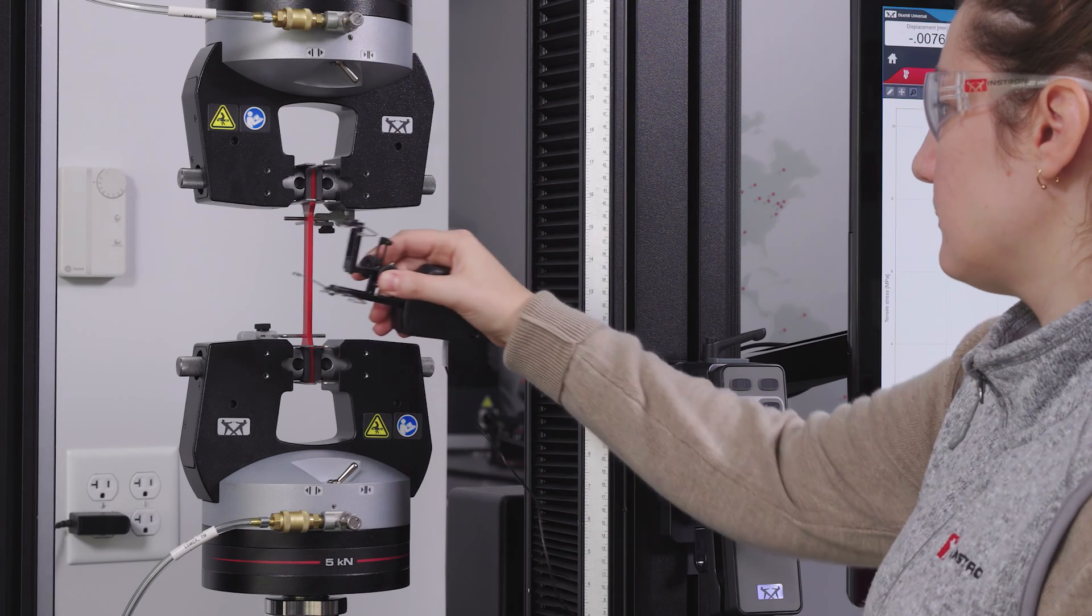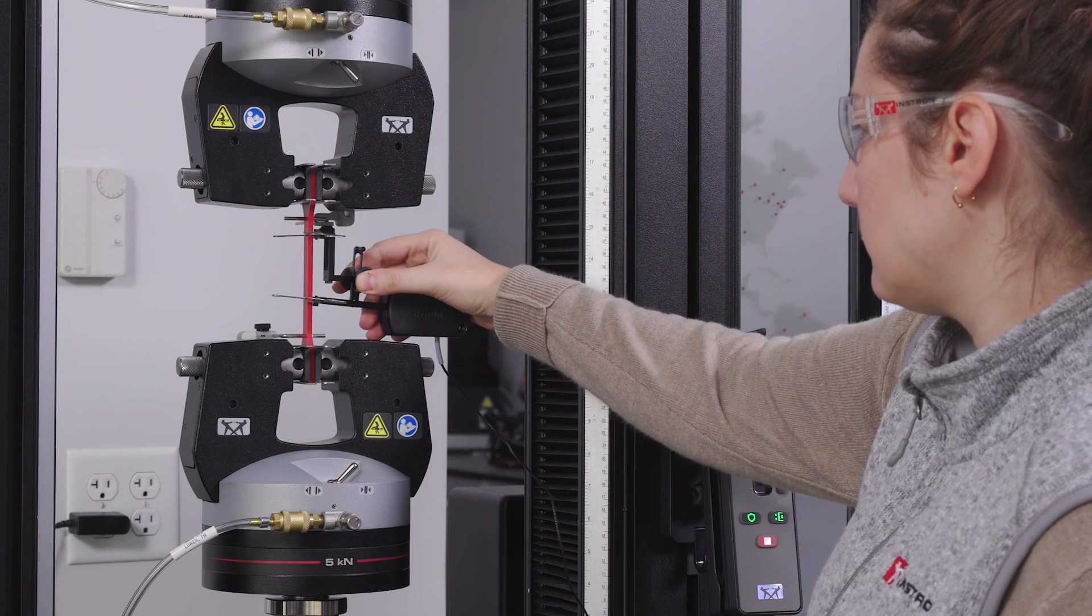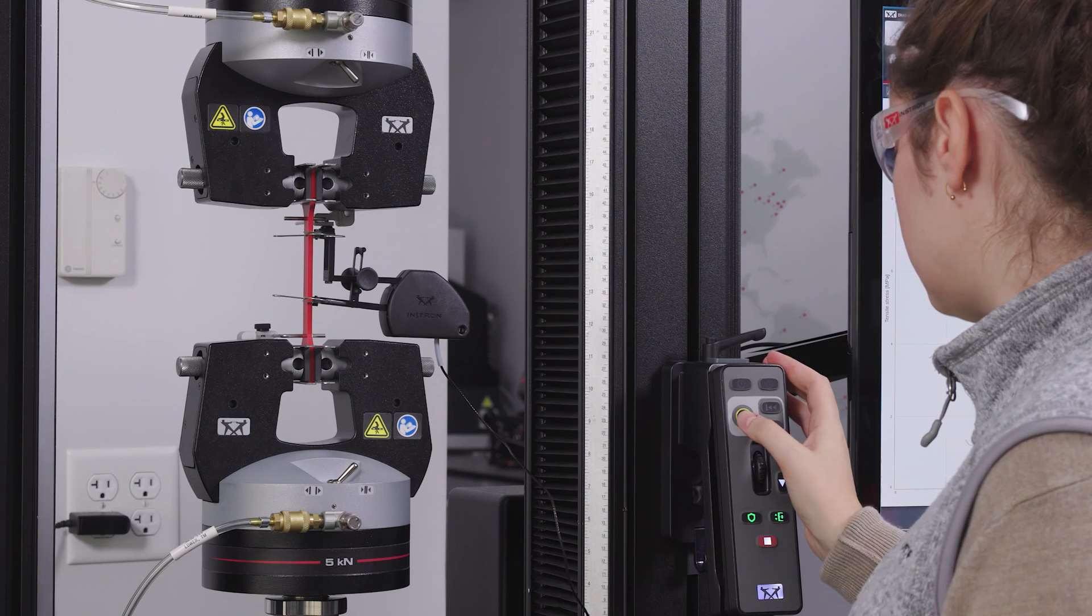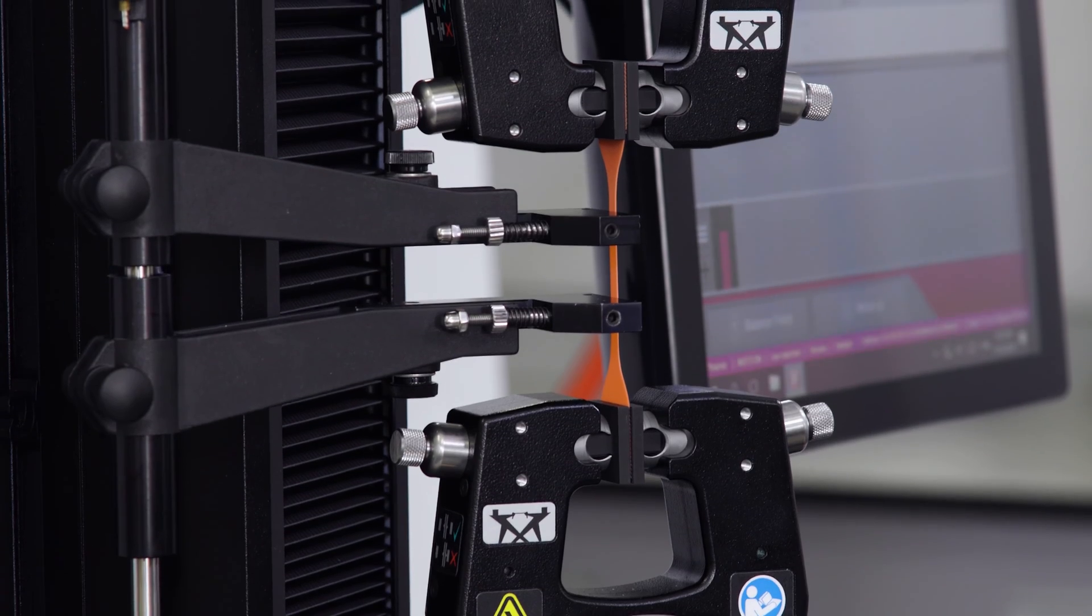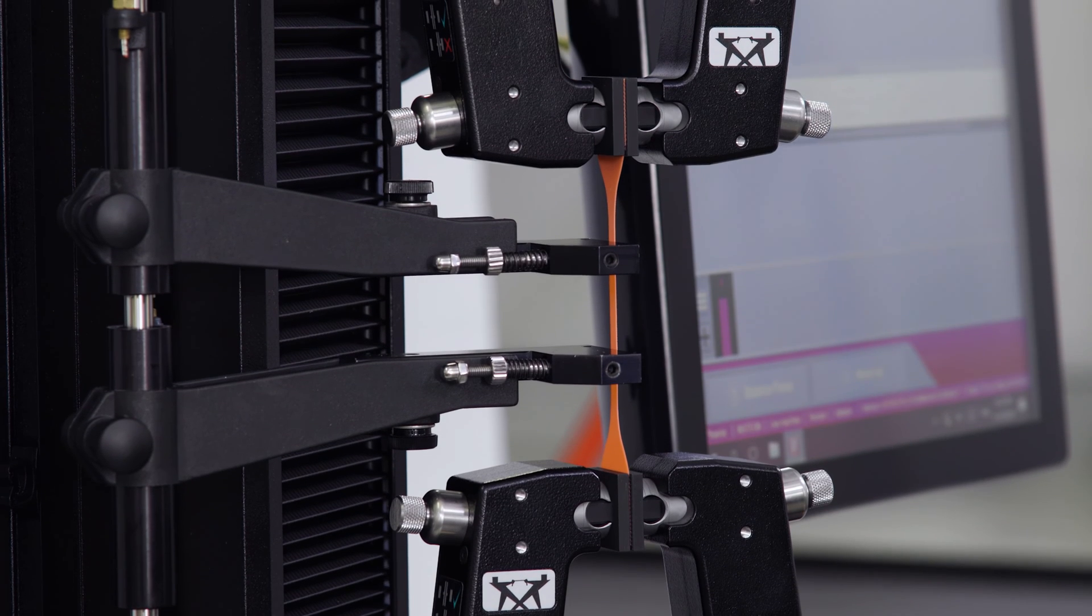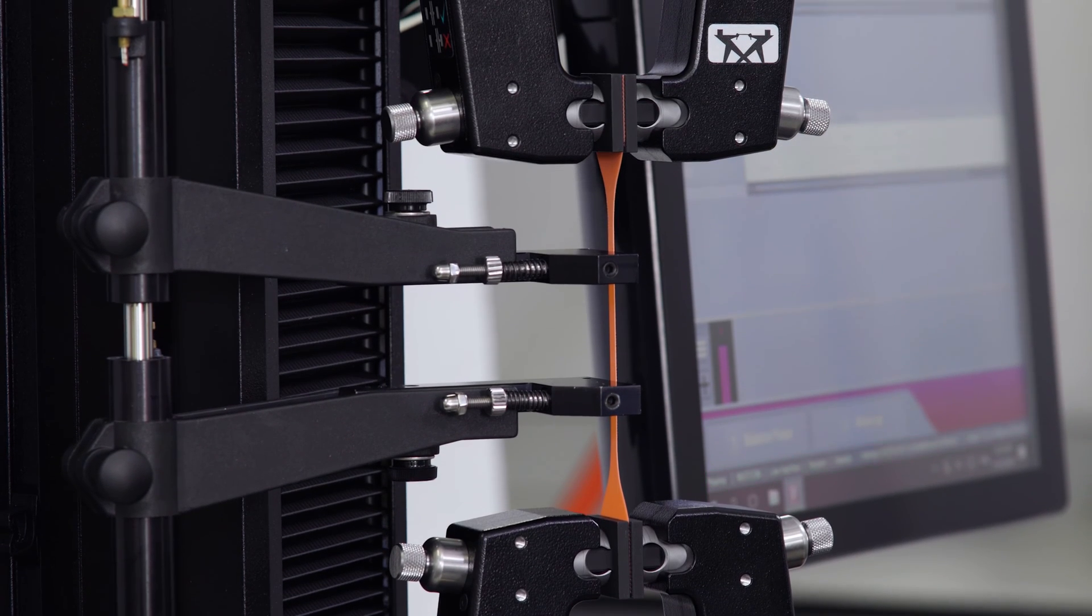Clip-on extensometers are cost effective options that are applied manually to each specimen by a test operator. These come in a variety of sizes but are generally restricted to materials that exhibit less than 100% strain. Manual contacting options are also available for elastomers and other high elongation materials.